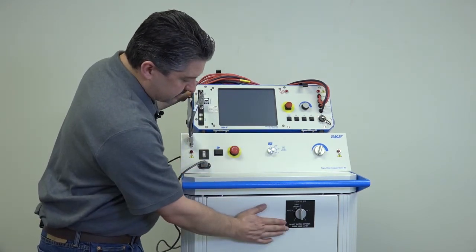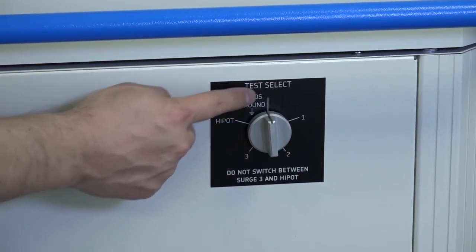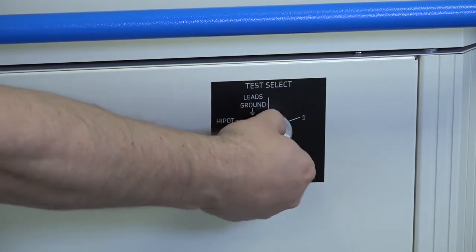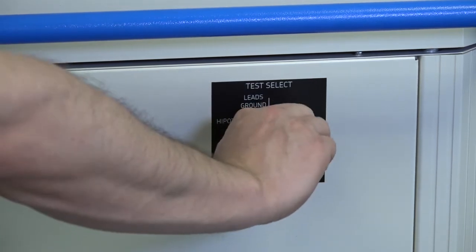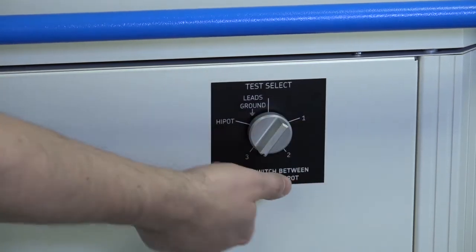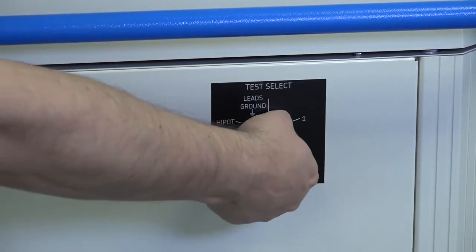On the faceplate of the unit, below the handle, we have the test selector switch. It has five positions: a high-pot for DC high-pot testing, a leads-grounded position, and positions one, two, and three that are used during surge test to put the surge down the appropriate lead.